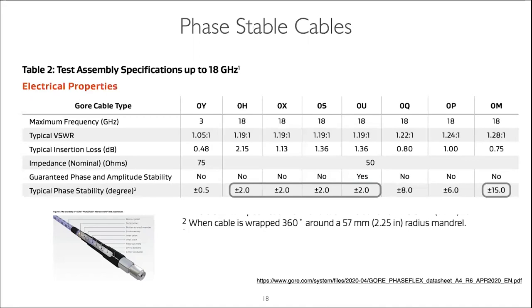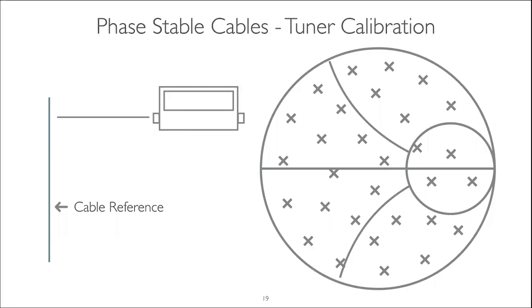Now, okay, there's a caveat. It says when the cable is wrapped 360 degrees, and in our case in load pull, we never wrap it around 360 degrees, but it just gives you the margin of error you could face if you're not careful. So how does that translate into tuner calibration and impedance presentation? Here's an example of a tuner with a gray cable, a cable that we're using, and we're just calibrating the tuner at this reference plane. Somebody that's used a tuner before knows you have these impedance points across the Smith chart. When you calibrate the tuner, you create this table of S parameters, and you associate the X, Y positions of the tuner to these sets of S parameters, right?